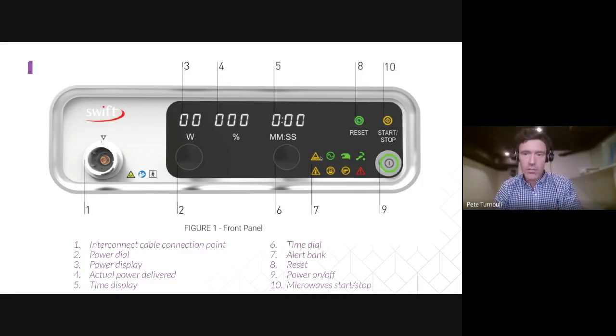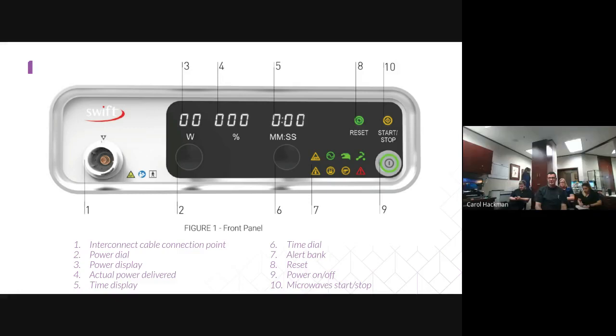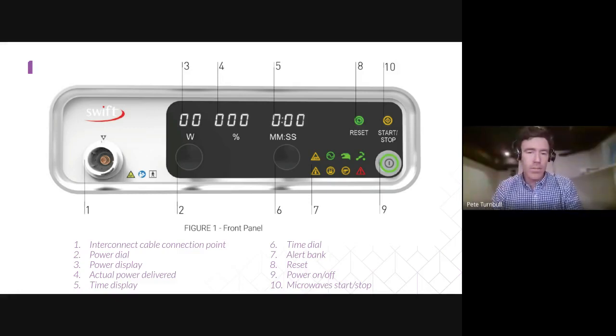You'll see this reflection error, this little triangle here on the left. And that means that the energy wasn't coming back to the system, and you just press reset and adjust your timer back to 2 seconds or whatever you want the treatment to be, and you deliver the treatment again. Okay. If you get that error, you don't want to turn the system off and then turn it on again, because you'll end up expiring the tip. So you don't want to blow the tip.